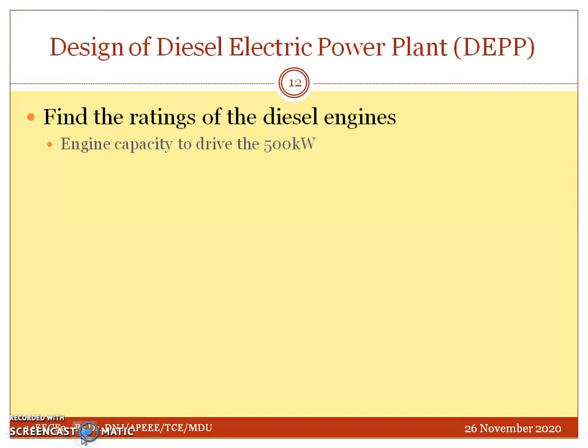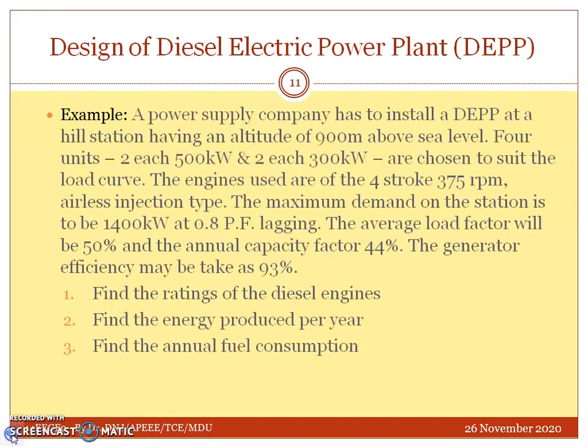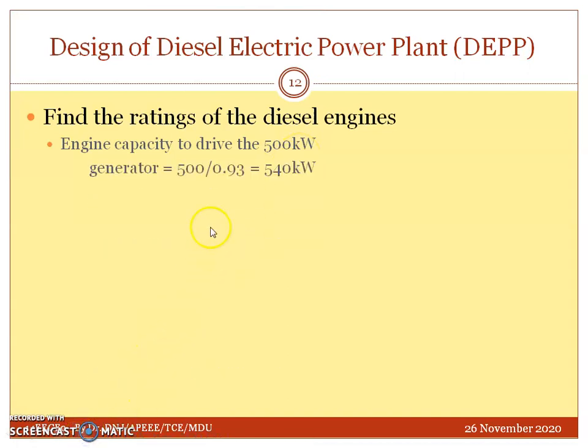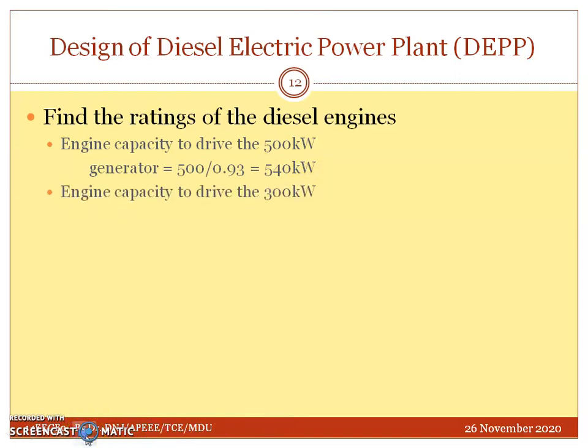For the engine capacity to drive the 500 kilowatt alternator: the required generator output is 500 kilowatt, so the input energy required is output divided by efficiency — 500 divided by 0.93 gives approximately 540 kilowatt. Similarly, for the 300 kilowatt machine, the input required is 300 divided by 0.93, giving approximately 322 kilowatt.